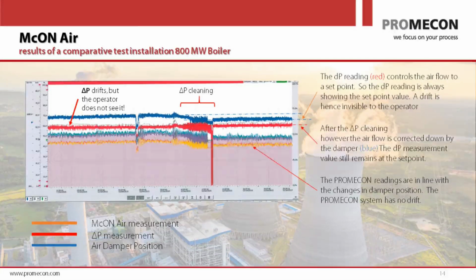This is another example. It's from a very modern boiler. It's an Alstom boiler, T-fired, 800 megawatts, ultra supercritical, with all the bells and whistles. And also, this boiler has an air heater, a single air heater, largest air heater in the world, and the same problem. You have congested airflows, and look at that red line. The red line is the DP. Now, it goes in a straight line, and it starts to be very noisy until someone goes out and cleans the impulse line. And after that, it's very flat again.